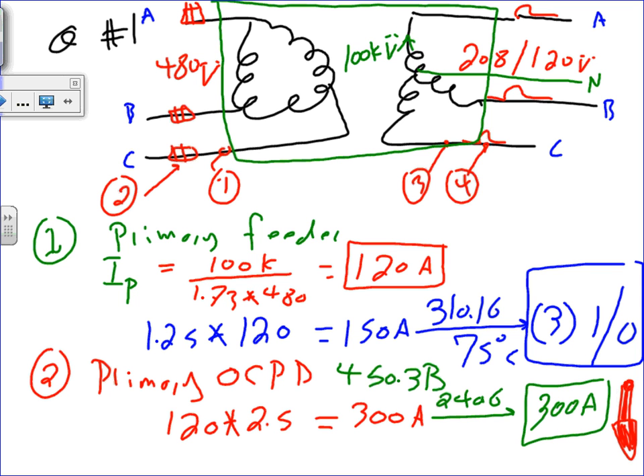Now, if you have a machine, though, here's where you can. Say you have a machine, and the machine is running at 208, I'm just assuming, and the voltage here is 480. You bring a feeder to the machine. Here's your transformer next to the machine, and from the secondary, you dump the voltage right through the machine. No panel, nothing. Then this is a good application for a primary only application, because you don't have a distribution system. You're just directly going on the 208 side and feeding the machine. One load. Any question, guys, for this transformer?